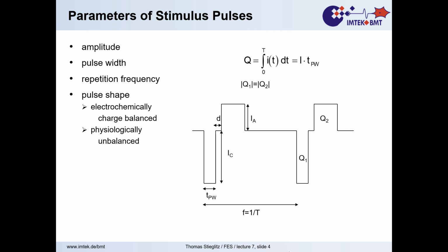And if you reverse the potential, the idea is to reverse all the electrochemistry that has happened. So you reverse the potential, and when you imagine water molecules have stuck to the surface, they go away again and you start with a pristine electrode for the next pulse.